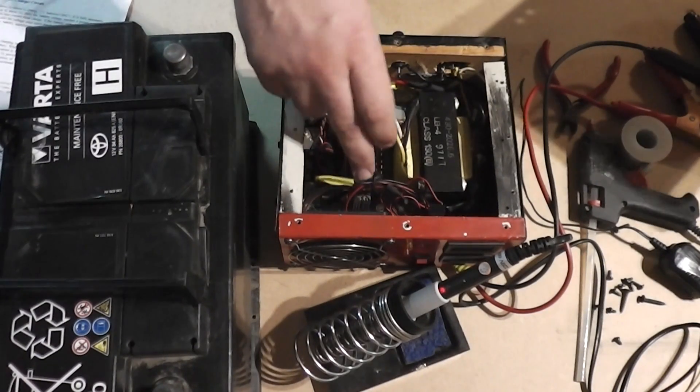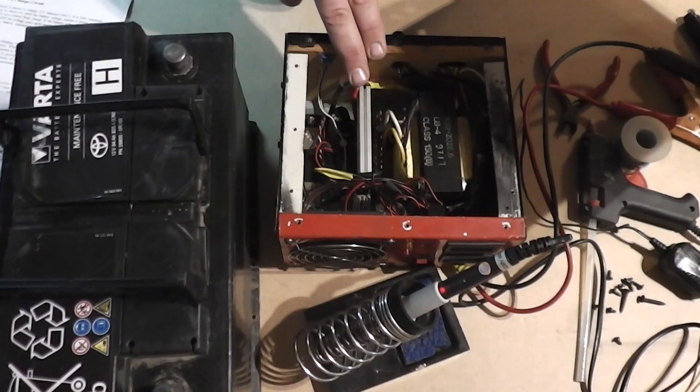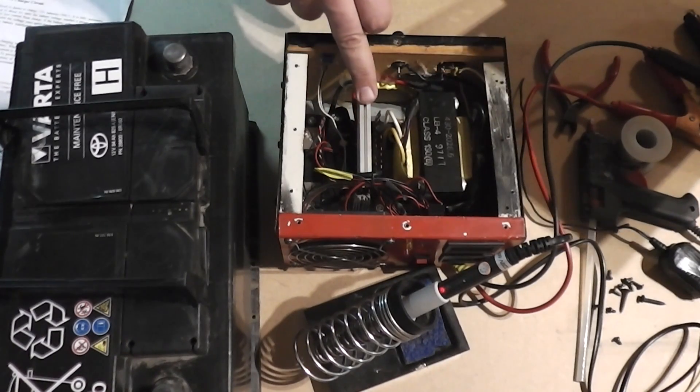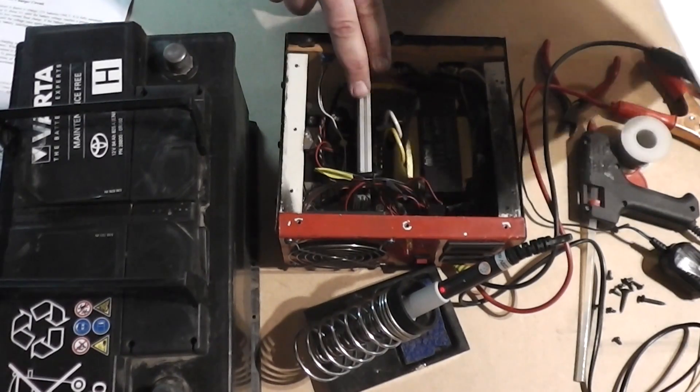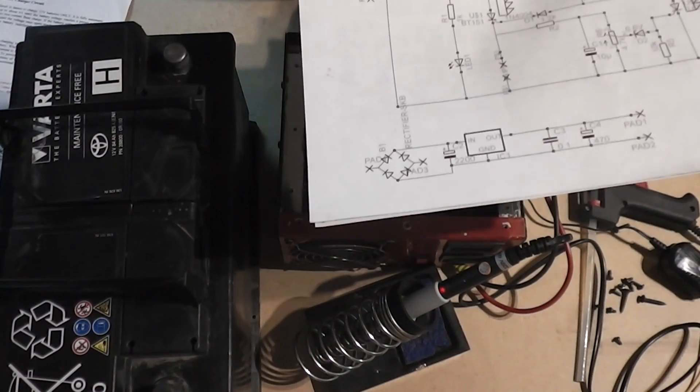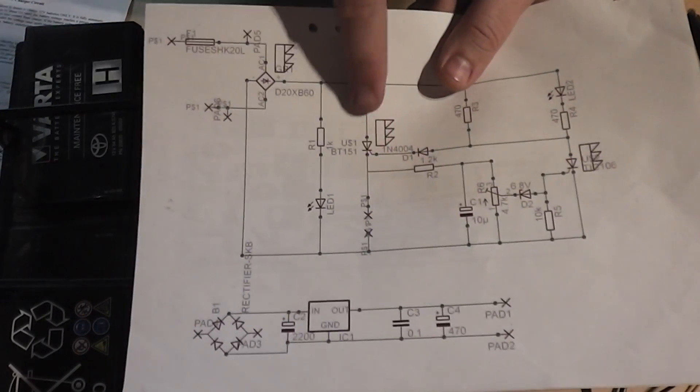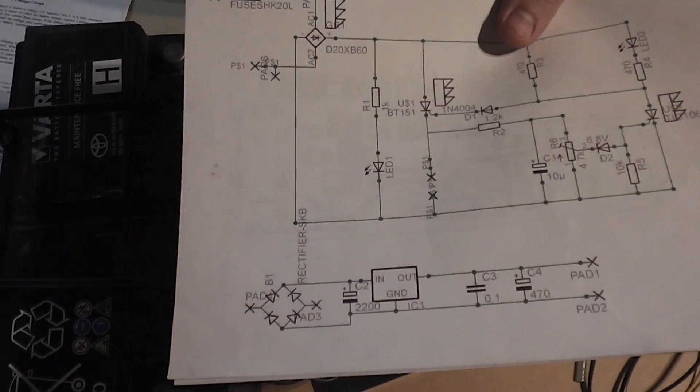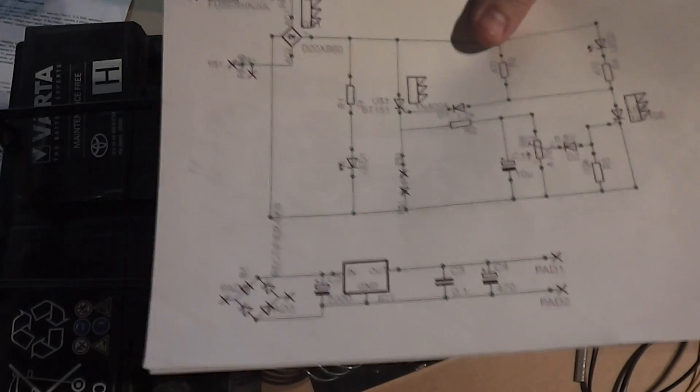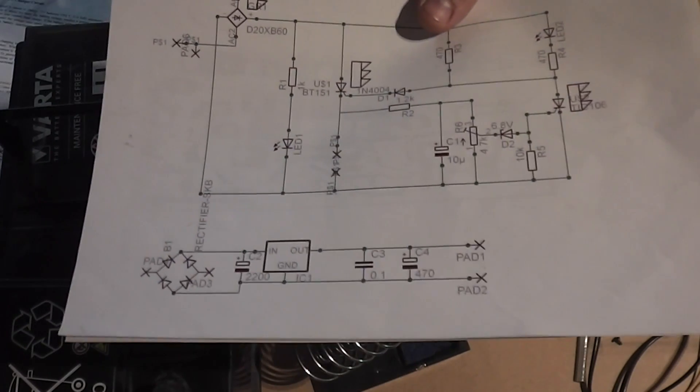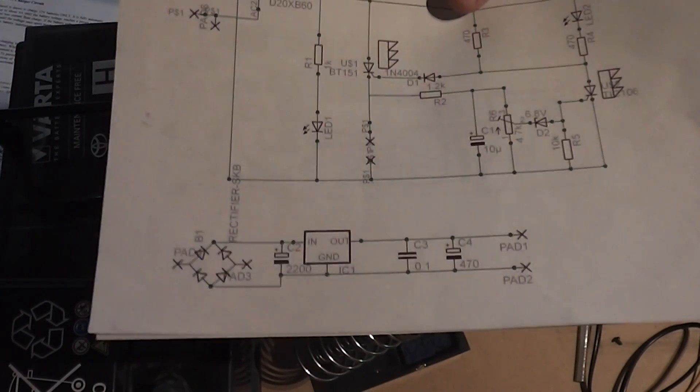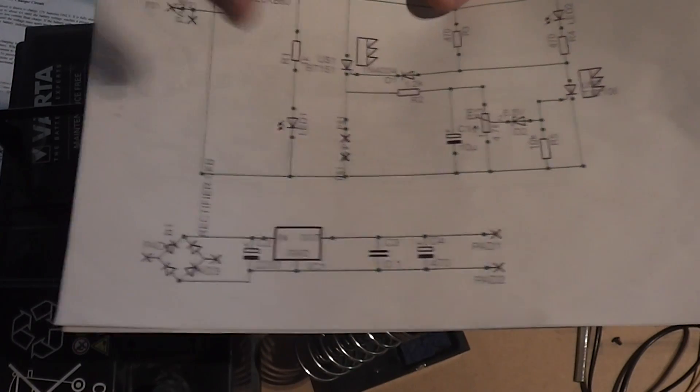Here down is the PCB board. This is the cooler, only a heatsink, not a big one, for the main thyristor silicon controlled rectifier. This one is controlling all current going through this thyristor and supplying the battery, charging the battery. This circuit here is controlling the gate of this main thyristor. It's switching on and off the charging process at a given state.